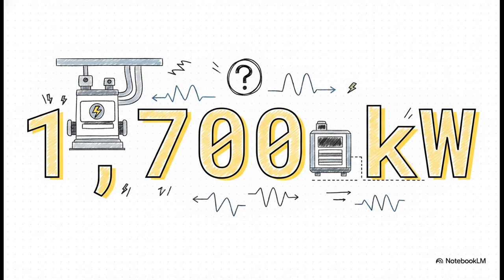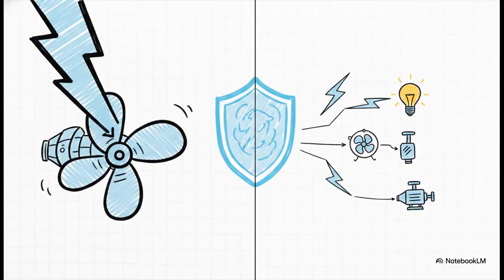But here's the catch. When that massive 42-megawatt plant goes completely dark, a dedicated 1,700 kilowatt STX Cummins emergency generator is standing by to save the ship. But wait a second, 1,700 kilowatts compared to 42 megawatts? Why on earth is the backup so deliberately small? Well, we're going to solve that mystery today. But to really appreciate it, we first need to understand what this ship's electrical system does when everything is actually working perfectly. So let's flash back to normal operations for a second.